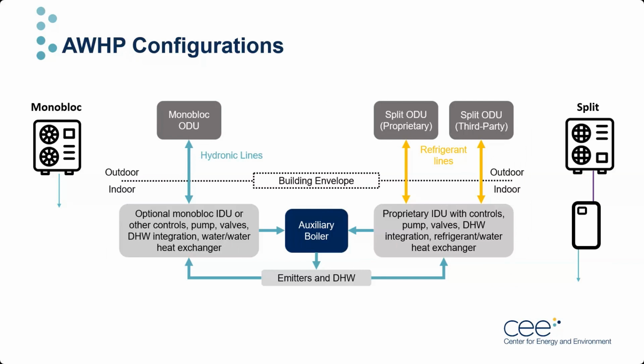This is then connected to whatever emitters are present in the home, be it a radiant floor, low temperature radiators, fan coils, or a hydronic coil for forced air heating. This is also where domestic hot water comes into play, as the system may supply preheating to a DHW tank as an additional output to the IDU.